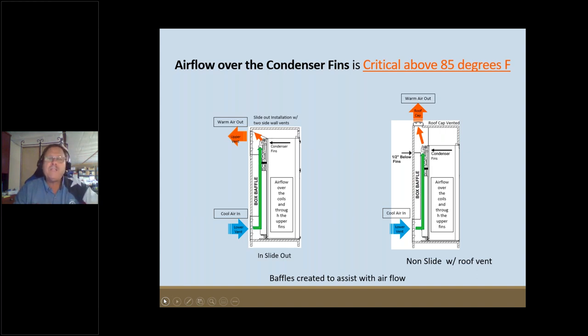There is a very strategic spacing requirement: the space between the baffle or baffle box and the coils should be no more than about half an inch — the thickness of your hand at the knuckles. If there's too much space behind the refrigerator, air takes the path of least resistance and bypasses the coils entirely without doing any work. By keeping the refrigerator no more than a half inch from the back wall, you force air through the coils.